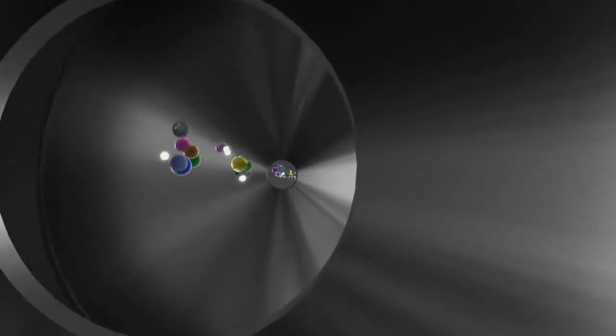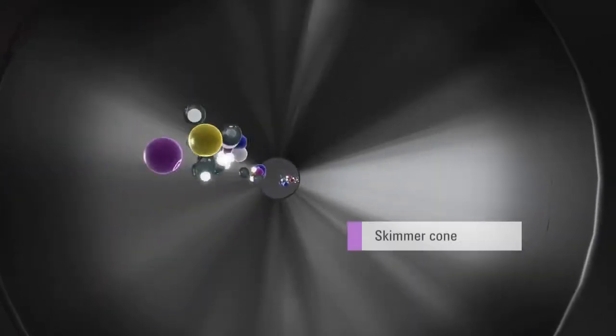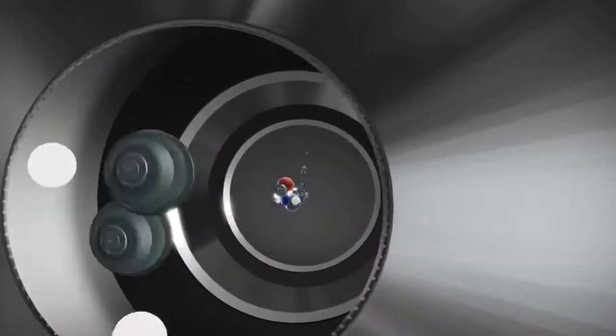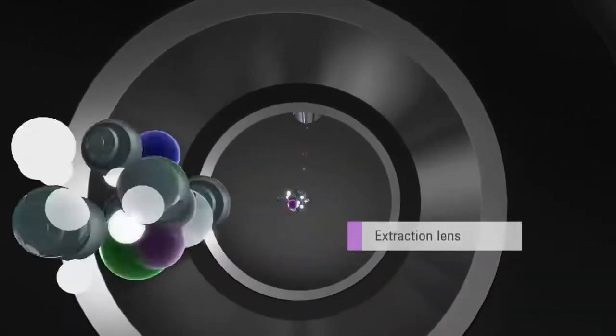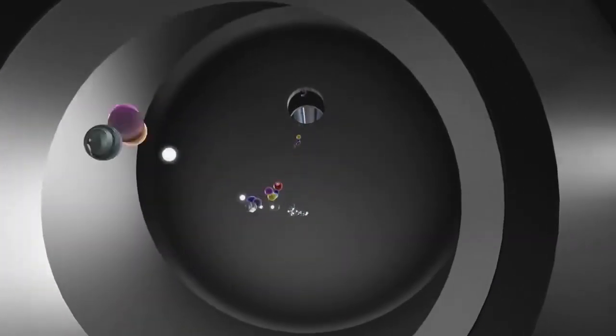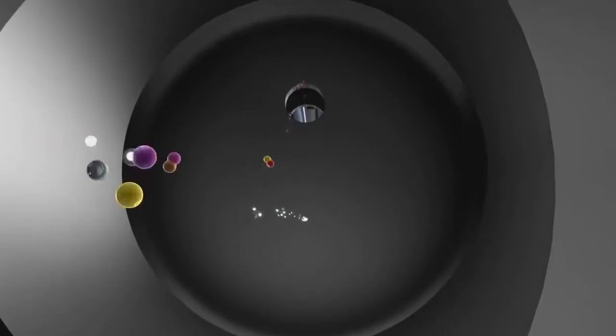Twin extraction lenses are mounted behind the interface cones and in front of the gate valve, so they can be accessed for routine maintenance without venting the vacuum system. The conical shape of the lenses reduces ion beam dispersion, delivering high sensitivity across the mass range, while also minimizing drift when measuring high matrix samples.